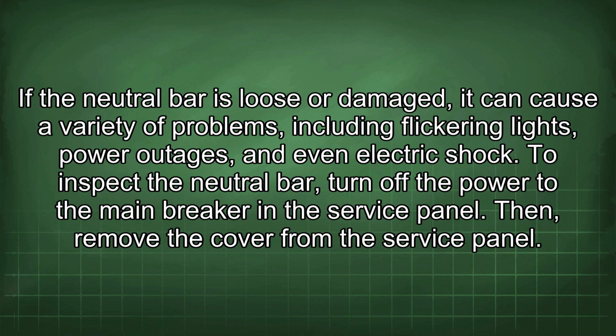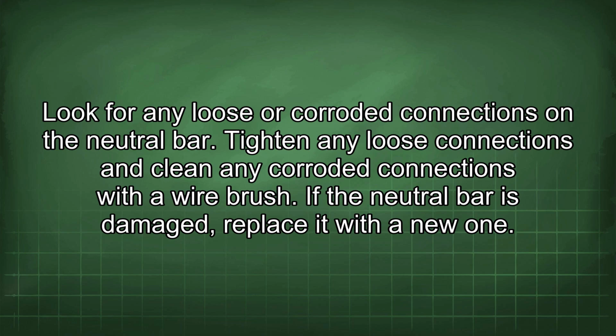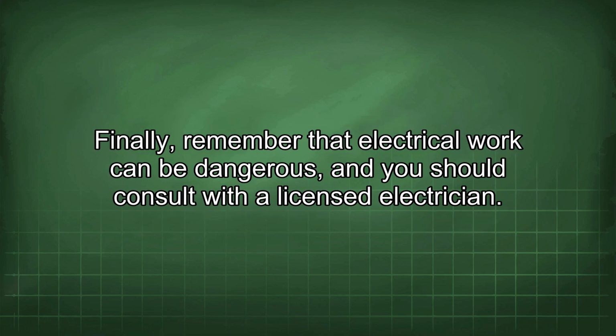To inspect the neutral bar, turn off the power to the main breaker in the service panel. Then remove the cover from the service panel. Look for any loose or corroded connections on the neutral bar. Tighten any loose connections and clean any corroded connections with a wire brush. If the neutral bar is damaged, replace it with a new one. Finally, remember that electrical work can be dangerous, and you should consult with a licensed electrician.